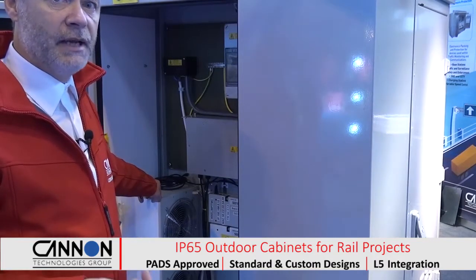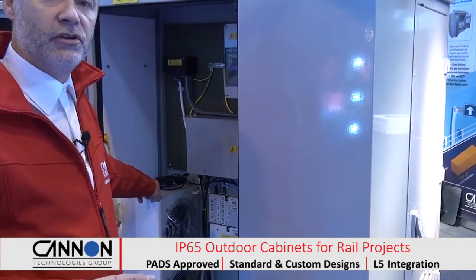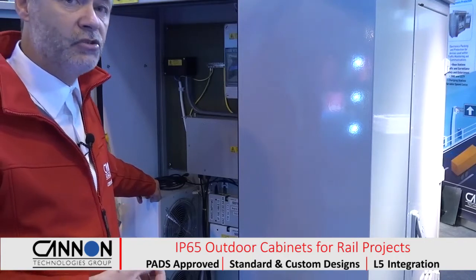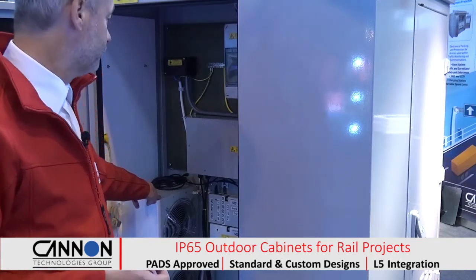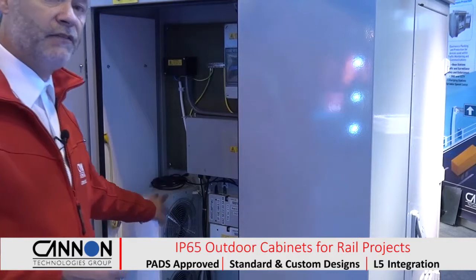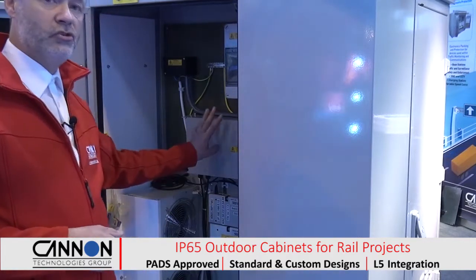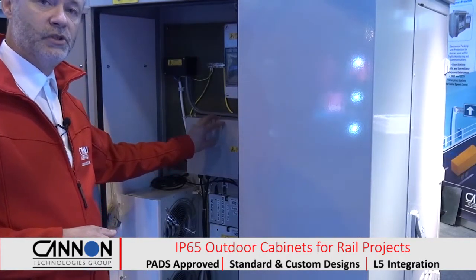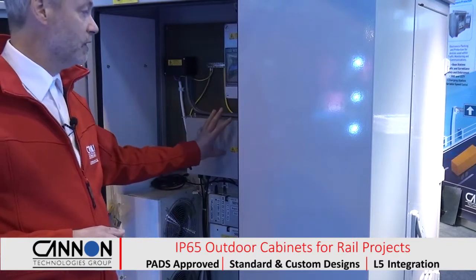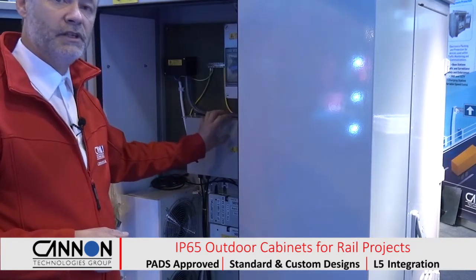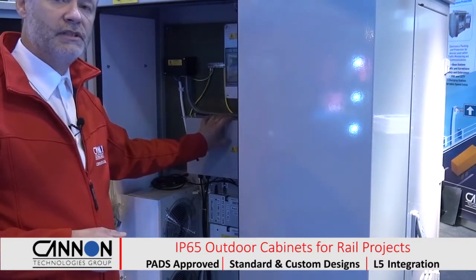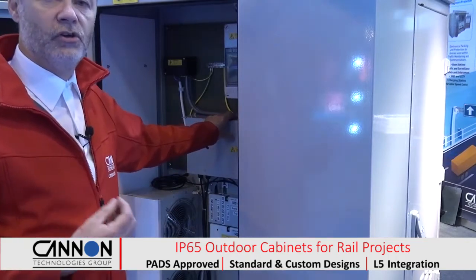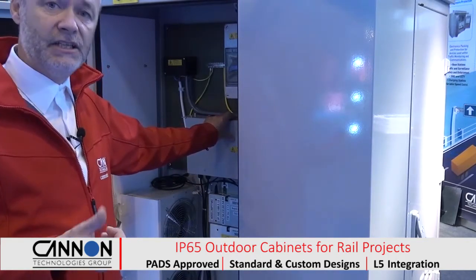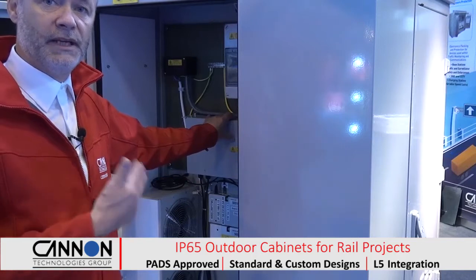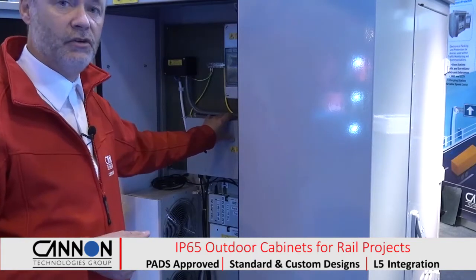Rapid changes of temperature can cause problems to the electronics, damaging them or causing failure very quickly. So this is the 48-volt fan version. We've got a control chiller card system which controls the fans and provides all the monitoring, digital and dry contacts, as well as being able to control relays, for example to turn a heater on and off during winter to maintain the right temperature inside the enclosure.